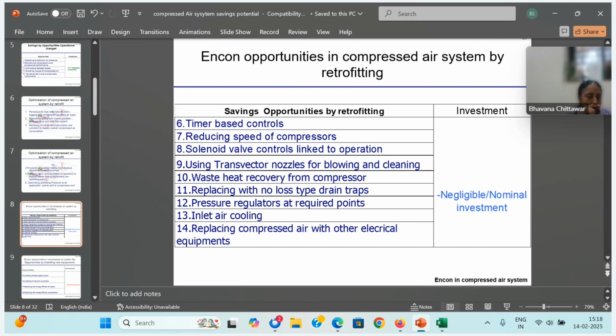I think more than 80% of plants require either hot water, or boiler feed water, or process requirements for heat treatment things. In fact, I have stopped some hot water boilers by recovering heat and giving hot water to the boiler feed water pumps. So many applications are there. Then space heating. In places like North India, during winter, they need hot air. So there we can take this hot air from the compressor for space heating. So that potential is always available in the compressors.